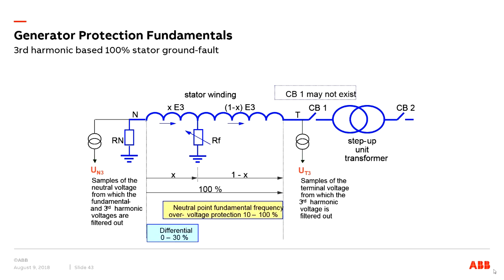Okay, here is another look at the connection. So we have the fault here, the fault resistance, and then we derive the third harmonic voltage from the neutral side and the terminal side. So the neutral point fundamental frequency over voltage protection provides protection for up to 90% of the winding, and the rest of the 10% is provided by this third harmonic principle, and we achieve 100% protection for the stator against ground fault.